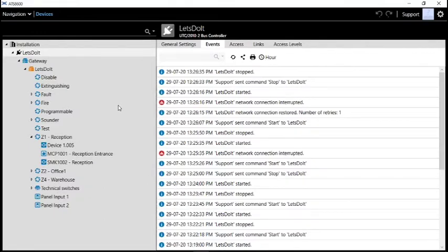And what you can see is at the top, that section is black. Again, it means there's some disconnect between the services, the fire panel, and the ATS software. All of that should either be blue or blue with the orange, which means it's a fault. In this case, there's definitely something wrong, and we'll need to investigate that now.